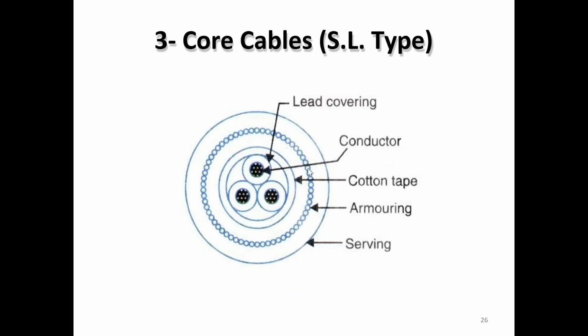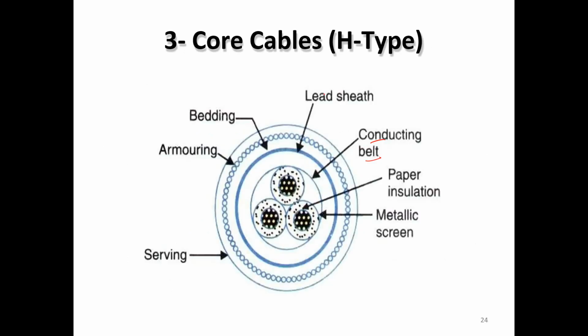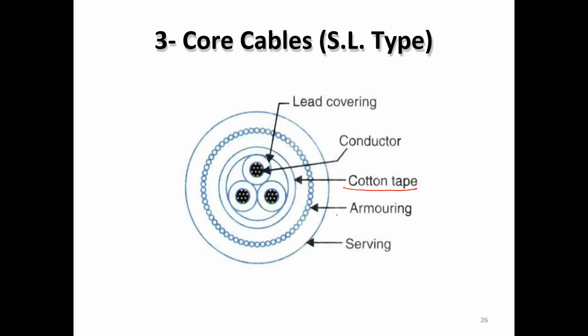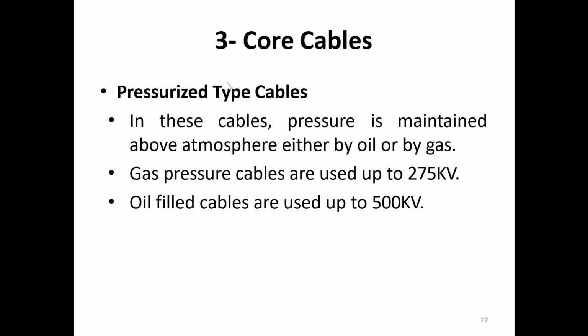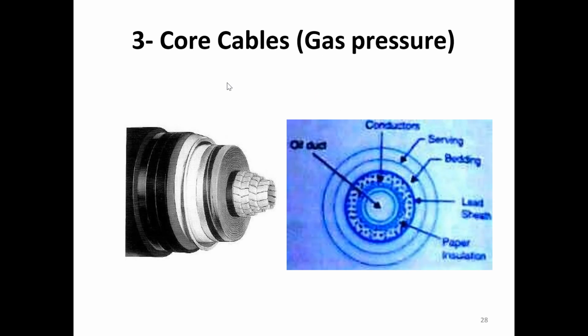If we go to the SL type, what will happen here? In SL type, again three core conductor, and for covering this, we use cotton tape. We use cotton tape, but here we use conducting belt. That is the main difference, or we can say the main constructional difference between SL type and H type construction of three core cable. Is it clear? Then other points you can study.